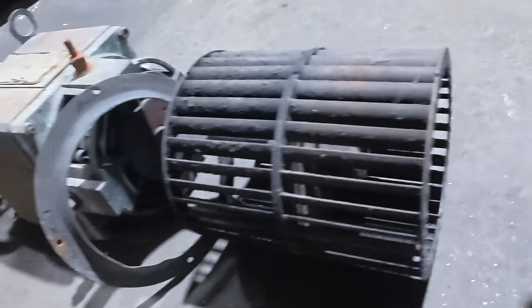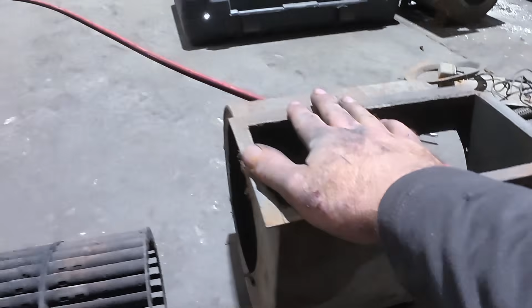So if you had great airflow, and somebody works on your bus and swaps the squirrel cages, or changes the motor, the motor runs but you have no air coming out of the vents. You need to double check which way they're installed. The easiest way to tell if it's working correctly is to pull the ductwork off and put your hand over the top of it.